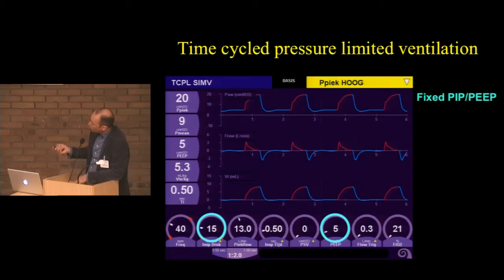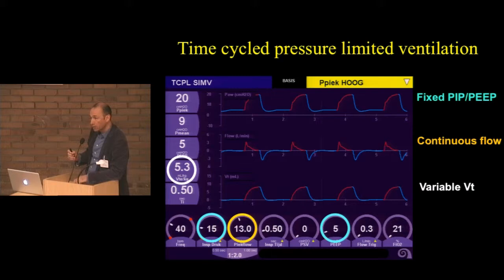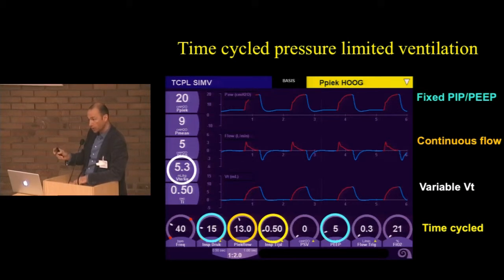So what we do is we set a certain PEEP level, an end expiratory pressure level. Above this, an inspiratory pressure rise, and this will give you a peak inflation pressure. This is fixed by the clinician. It has a continuous flow to build up the pressure difference, and the tidal volume that is delivered to the patient during time cycle pressure limited ventilation is variable. It depends on the compliance, the resistance, but also the spontaneous effort of the baby during ventilation. And it's time cycled, which means that the end of inspiration is based on the time that is set by the clinician. And this is why we call it time cycle pressure limited ventilation.